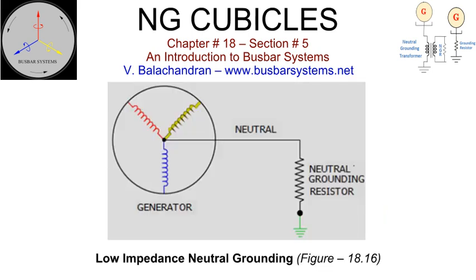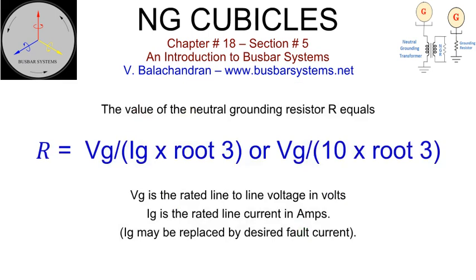Neutrals for smaller sized generators can be grounded directly through neutral grounding resistors with the line to ground fault current limited to either the rated current or, more commonly, 10 amperes for a fault at the generator terminals. Low impedance grounding is recommended for small sized generators. For small diesel generators, it is also a practice to connect the neutrals of several generators running in parallel and ground them through a common resistor. In the equation, Ig shall be substituted for a total ground fault current. It is sufficient to rate the neutral grounding resistor for a short time duration of 10 seconds or 60 seconds.